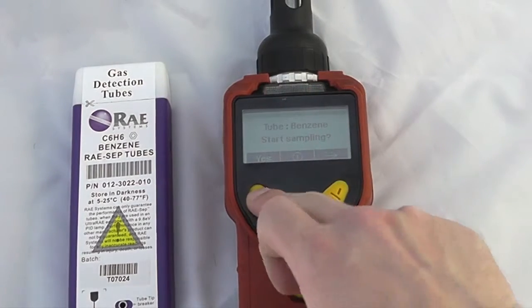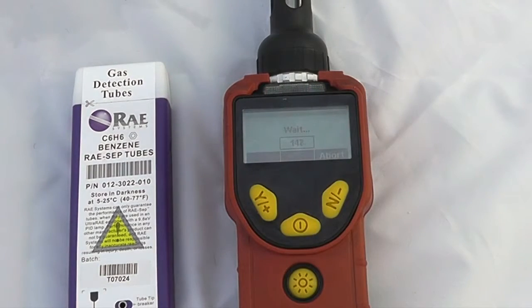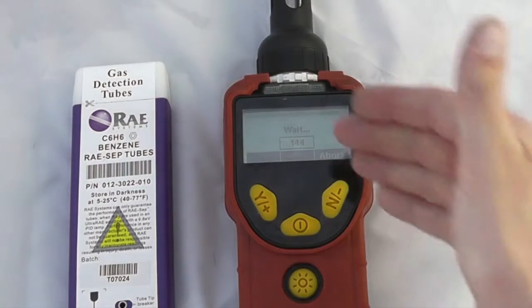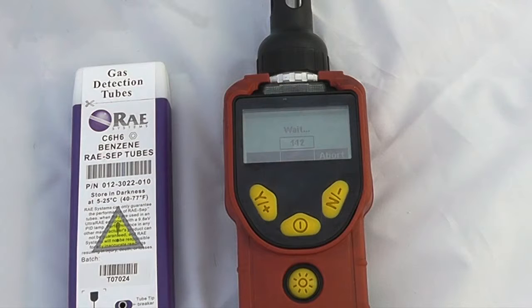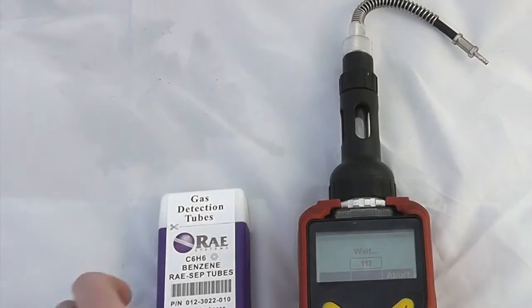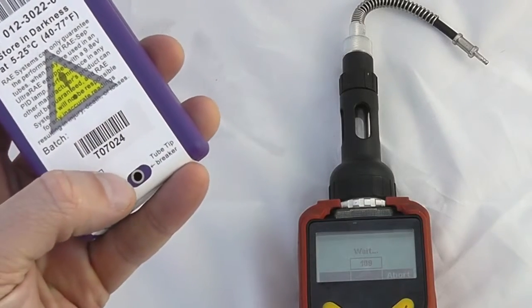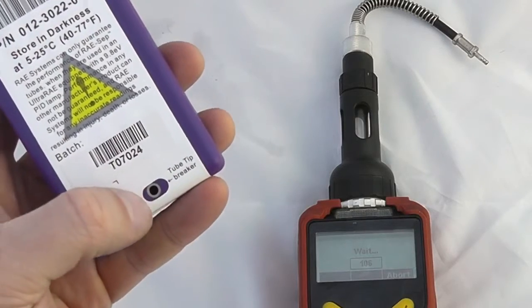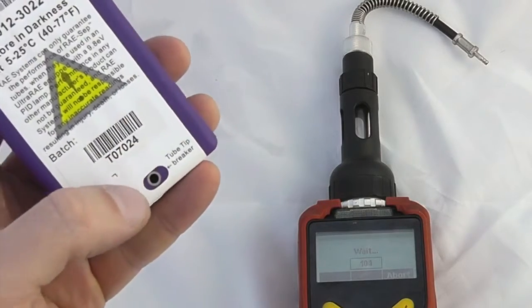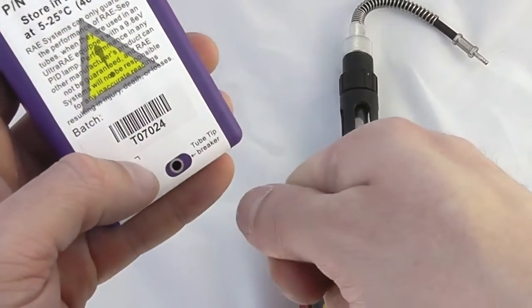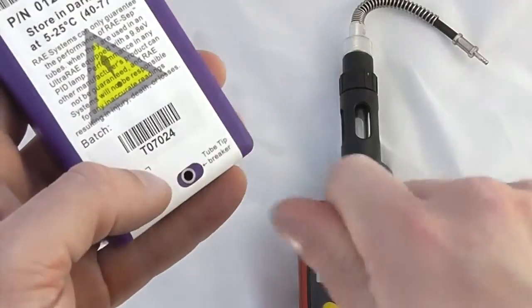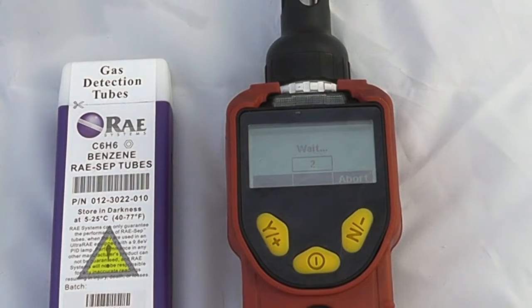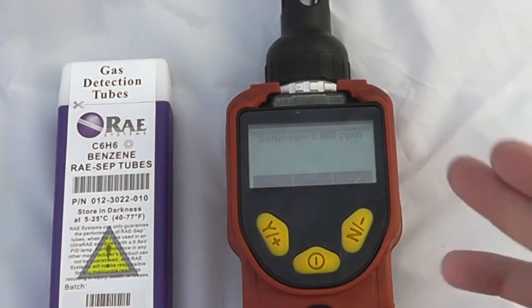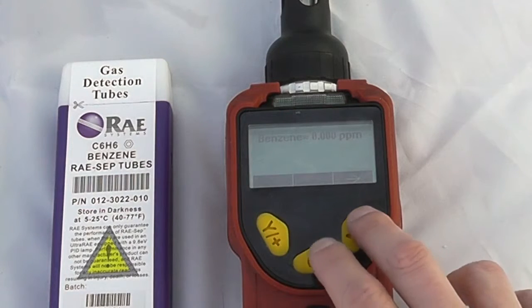When we want to do a tube measurement, press yes, and then it will take 150 seconds to do a benzene measurement. The end of this is dependent on the temperature of the instrument itself. At the end of this time, it will give me a live benzene reading. There is a tube tip breaker built into every box of tubes, so this helps to break the tips off and contains any sharps in the bottom. We spin the tube in there, that creates a film around there, and then you can snap the tube off. So now we're at the end of the benzene measurement. We should get a benzene reading at this point, and I can see I'm reading 0.0 parts per million.